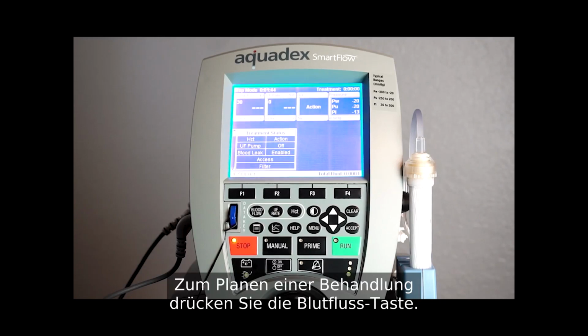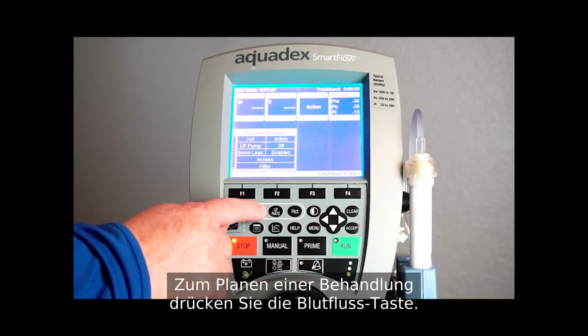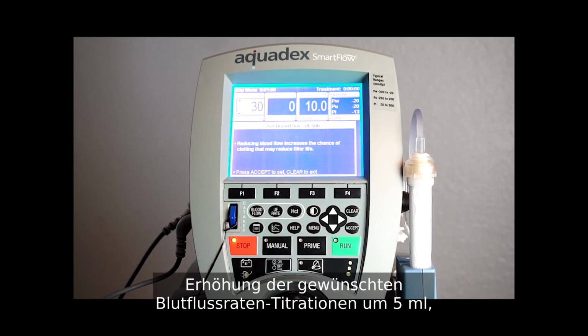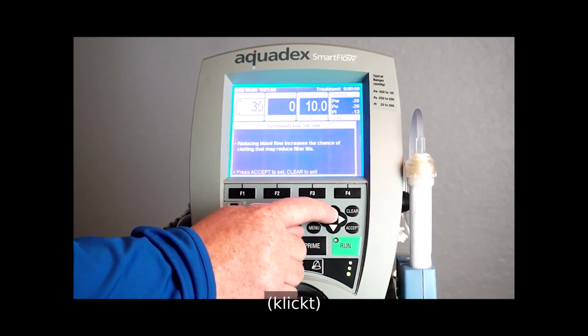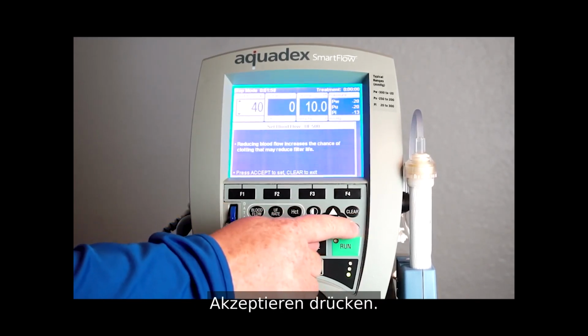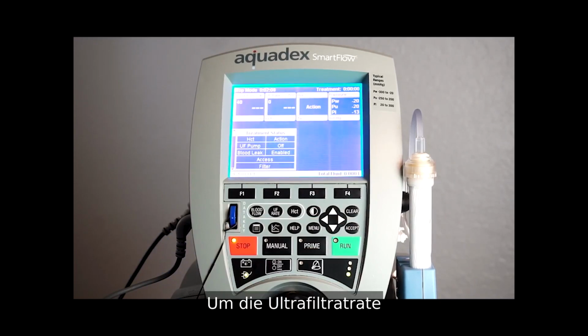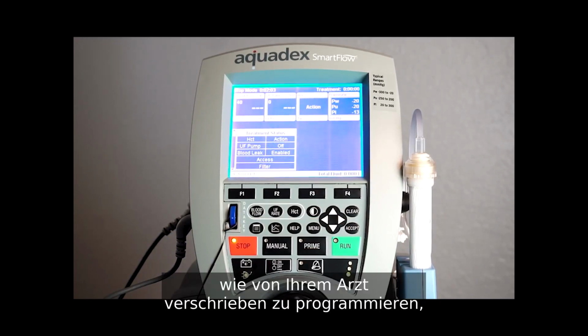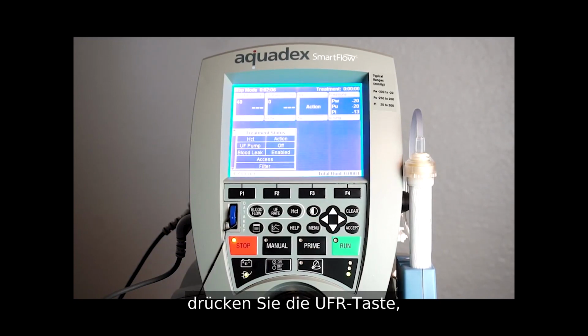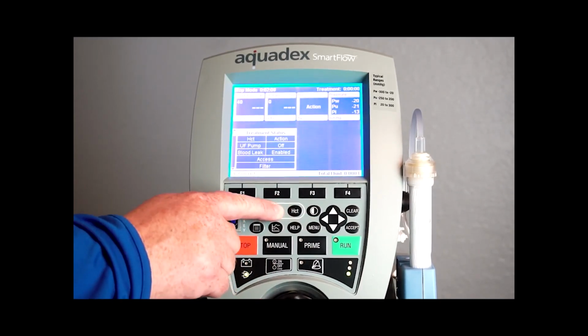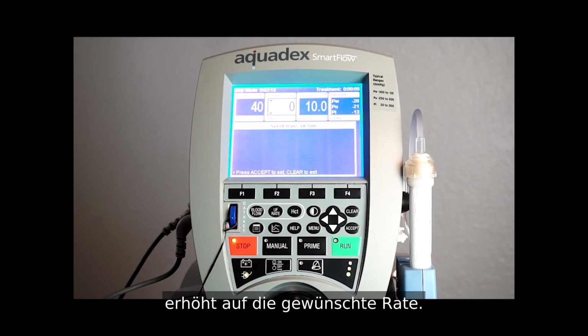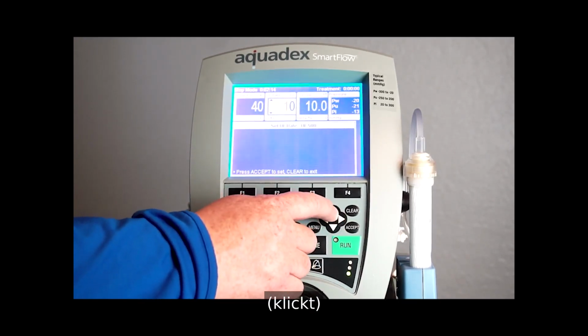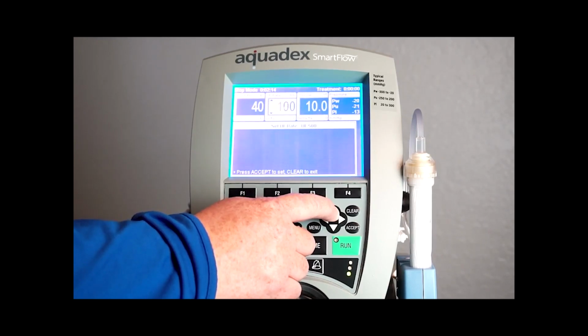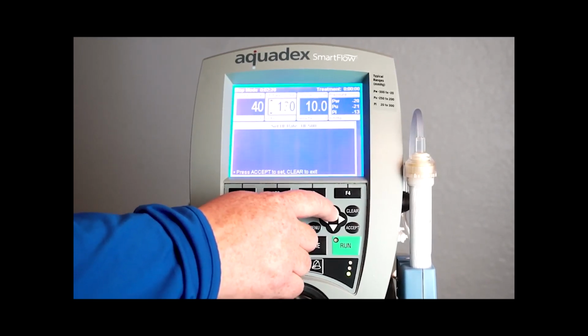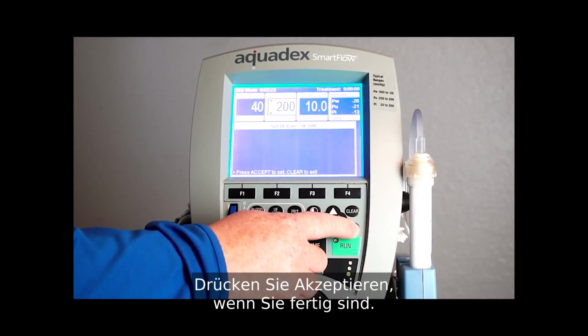To program a treatment, press the blood flow button. Increase to desired blood flow rate. Titrations by 5 ml. Press accept. To program ultrafiltrate rate as prescribed by your physician, press the UFR button. Increase to desired rate. Press accept when complete.